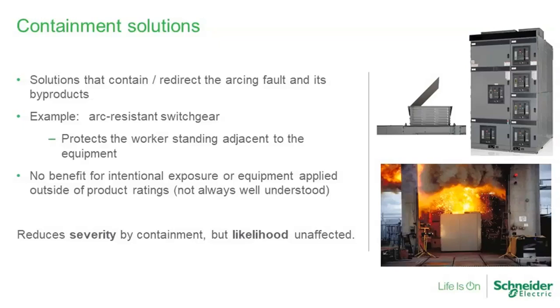In a way, you can think of the PPE as being built into the equipment. There may be heavier gauge steel. As you can see on the bottom, the hot gases and flames are shooting out the top. In a lot of these systems, you have some kind of ducting on top to vent those away from the vicinity of the gear itself, out to somewhere where nobody is standing, and provide some significant protection that way. Certain industries use arc-resistant switchgear on a pretty extensive basis, oil and gas, the utility segment. Others, not as much, but again, it does some nice things for you. But it doesn't solve every problem that you have.